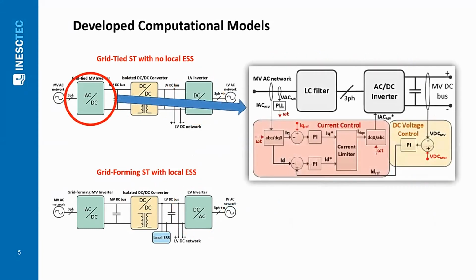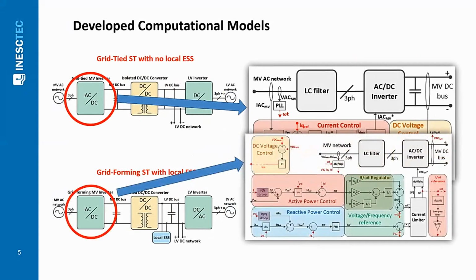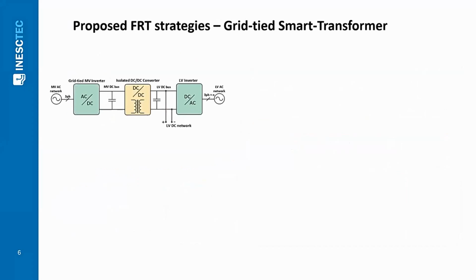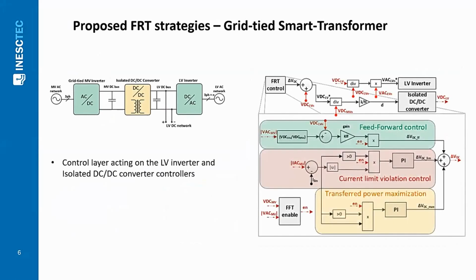In the grid-tied smart transformer, the medium voltage inverter is tied to the upstream system voltage, controlling its output current, while the medium voltage inverter of the grid-forming smart transformer controls the frequency and magnitude of its output voltage. Now follows a description of the proposed fault ride-through strategies, which are the focus of this work. The fault ride-through strategy for the grid-tied smart transformer constitutes an additional control layer acting on the controllers of the low voltage inverter and isolated DC-DC converter, as illustrated in this slide.